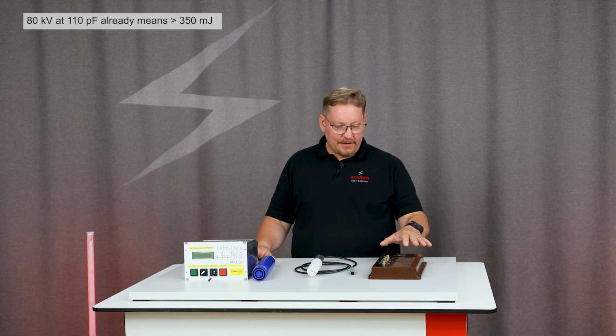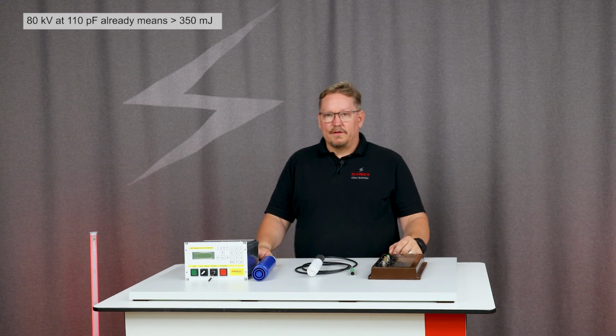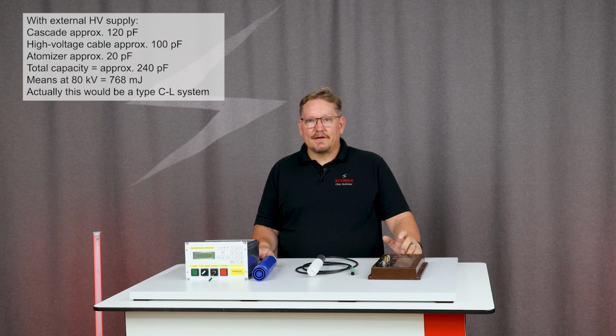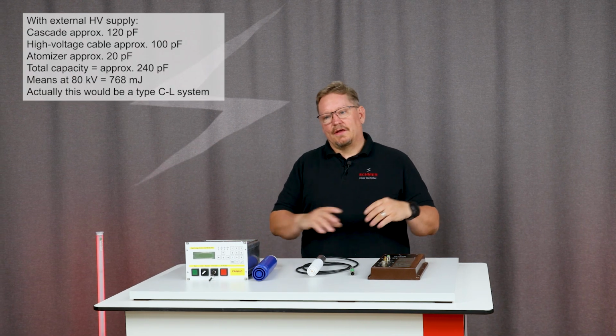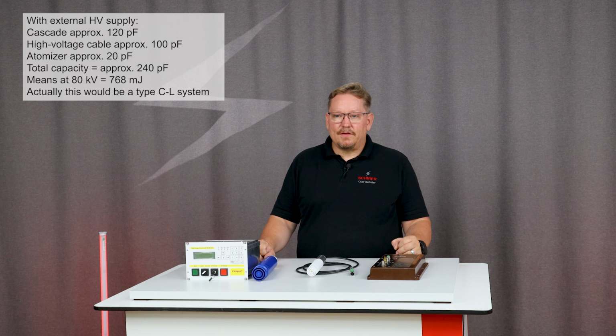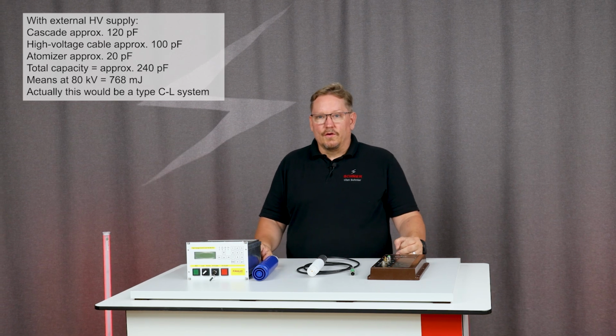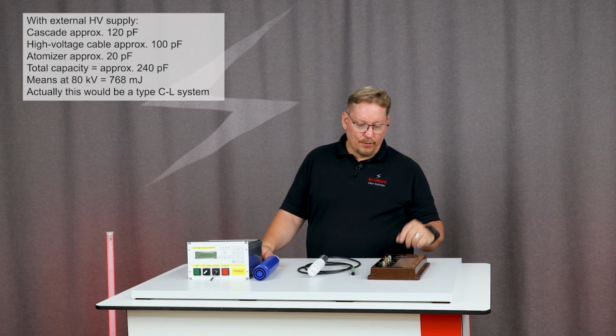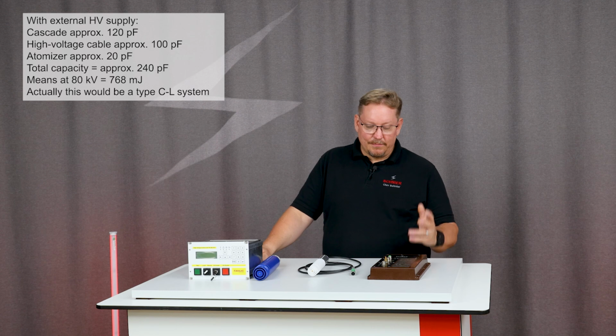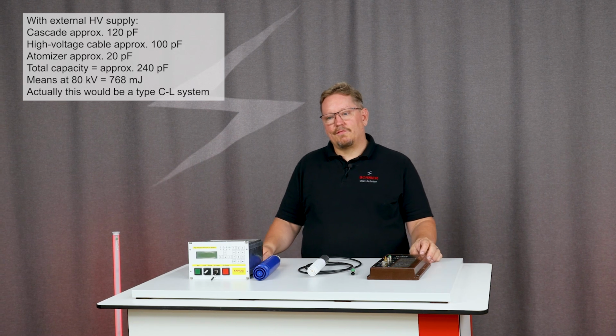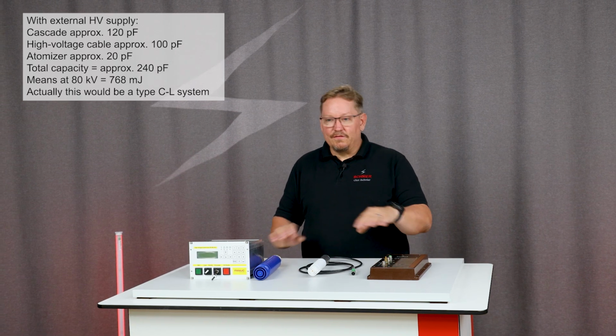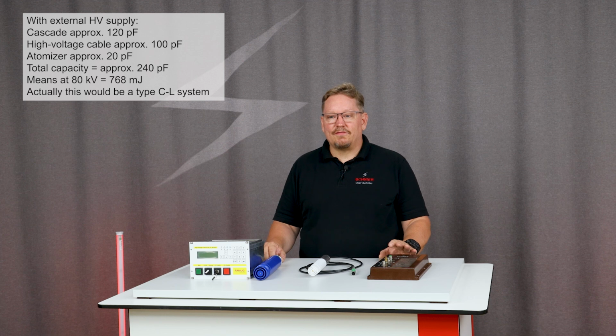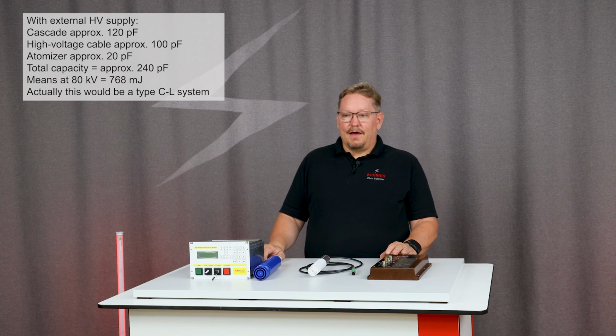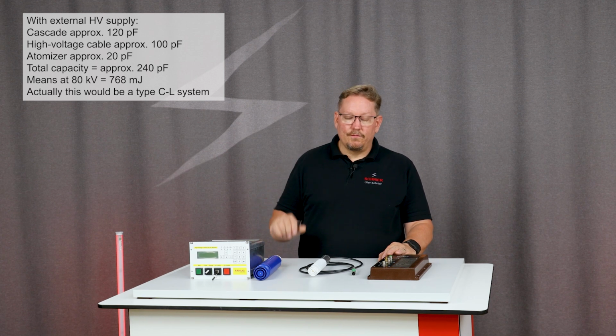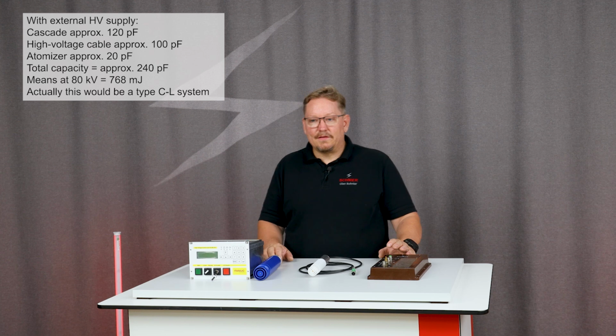If we now take the system here, then we have a capacitance of 120 pF somewhere in the cascade. Then there is also a high voltage cable, 2 meters, plus perhaps another 100 pF, plus the 15 to 25 pF from the atomizer. Which means that with 80 to 90 kV, we are definitely in the range of over 350 millijoule. And we can't do it with such a system.